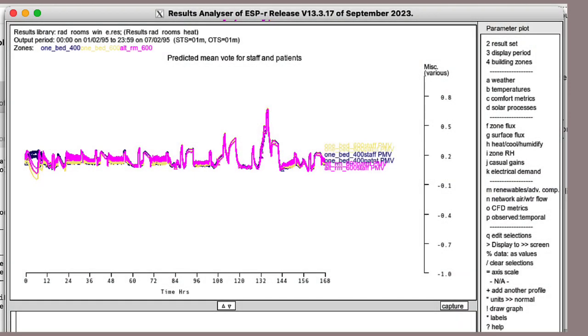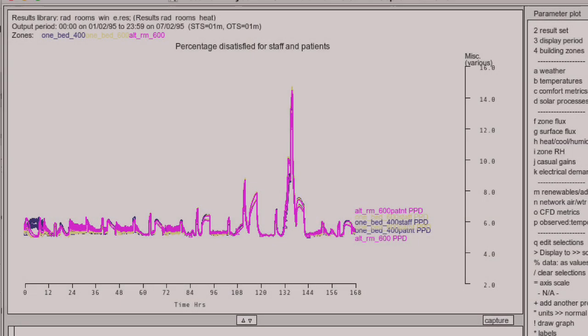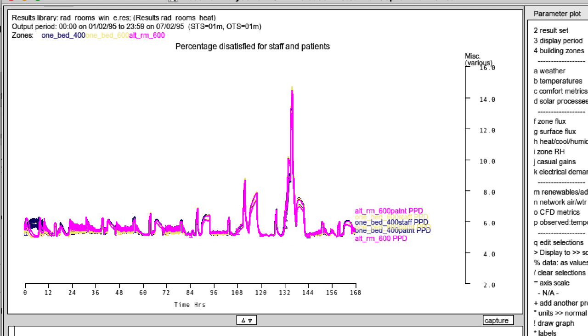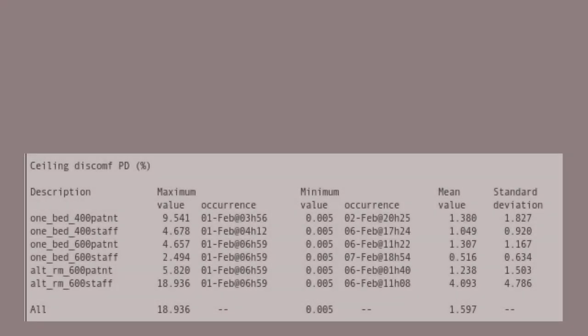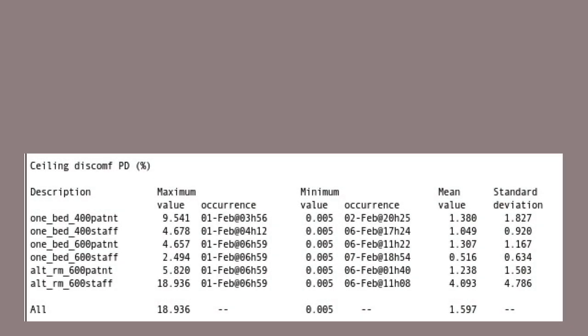Here's a graph of predicted mean vote. And there's not much change except for just a few hours of one day. If we look at percentage dissatisfied, especially related to asymmetrical discomfort, not much change. But when there is one in that alternative room with the panel much closer to the head of the staff, bang, we see it. Clearly, shifting that panel closer to where the staff was standing, it's not really a good idea.